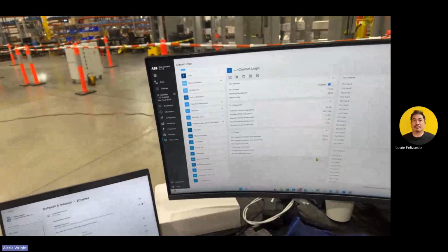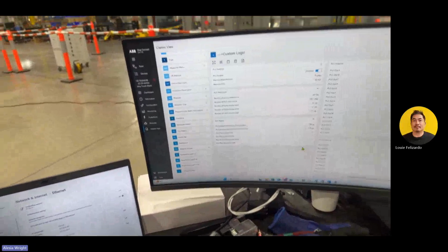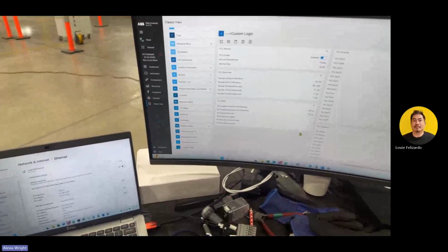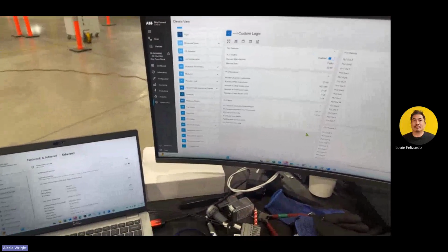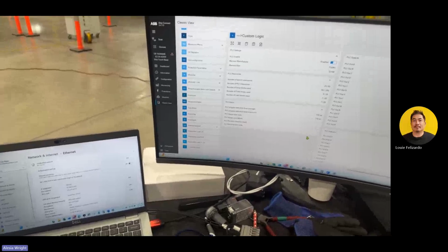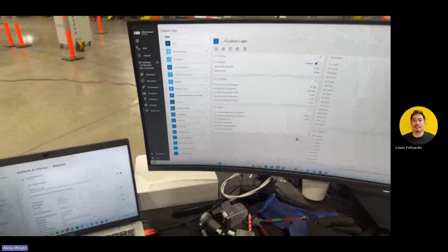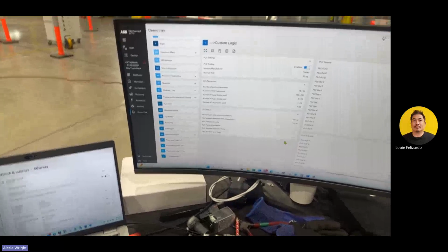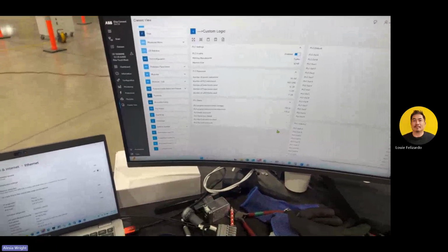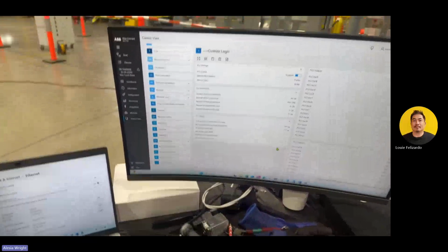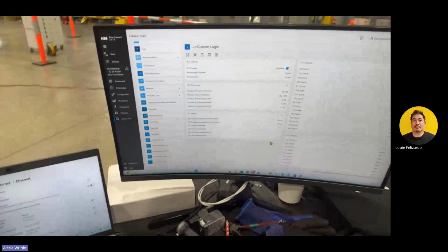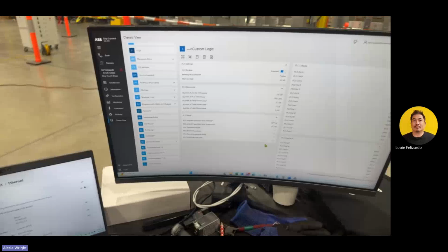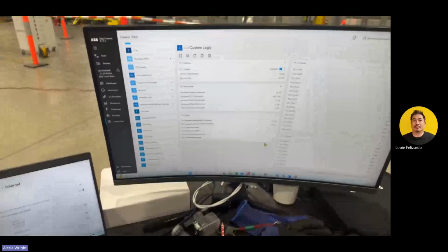Make sure none of your batteries are connected. You have to turn off all the power to the unit. So make sure the 24-volt batteries at the bottom are disconnected. Not all units have both sources with batteries. Source 1 and 2 may have batteries, but if you do have them, make sure both batteries are disconnected. That means there's no power to the unit at all.